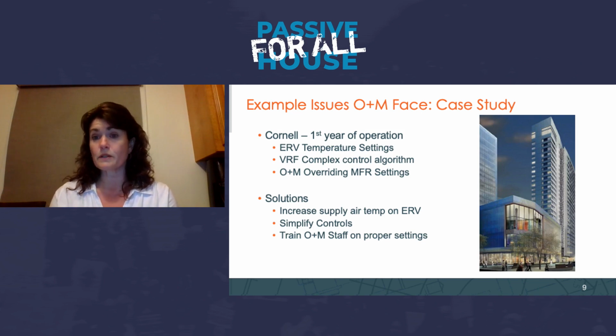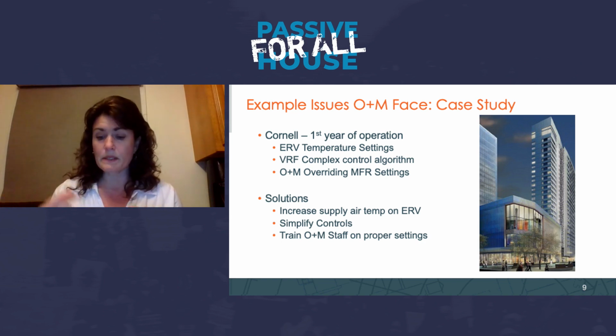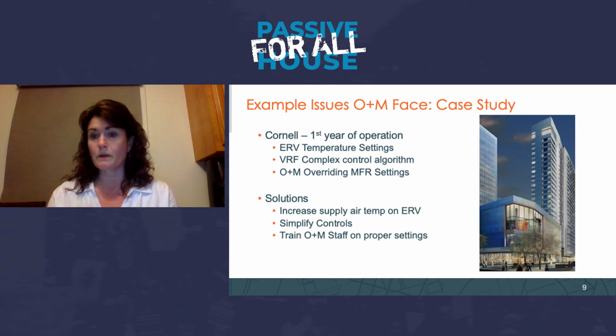So Cornell was the first large-scale multifamily passive house project that we had completed. And in the first year of operation, they ran into some difficulty. And again, the O&M staff wasn't really prepared to deal with it. There are very large central energy recovery ventilators on this building, two generally on the roof, that are handling most of the residential dwelling units, as opposed to the common areas. And they had a post-heat function in the winter, so that they would warm up the air before it went to the apartments. And it was set somewhere in the mid to upper 60s. Well, occupants found that was a little too chilly in the swing seasons, right? So there was an issue of comfort there.